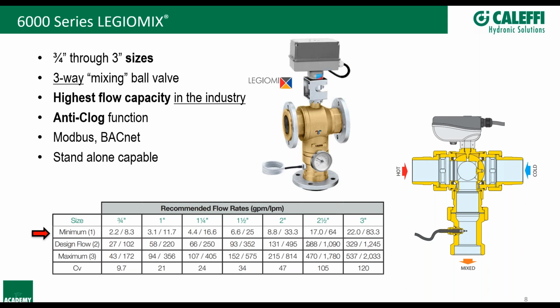So what do you do about that? I will tell you, in a lot of cases, most design flow rates, if they're based on any type of Hunter's curve, are pretty generous. So you might be more apt to look at the 2-inch model, even though its design flow rate is 131 and your design flow rate for that application is 190. How often are you going to hit that? And we're still capable of handling up to 215 gallons per minute.